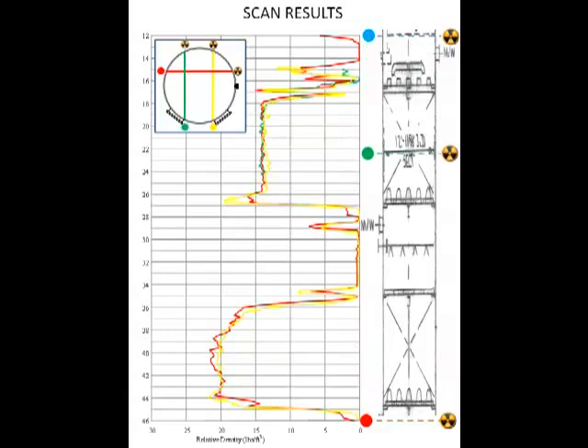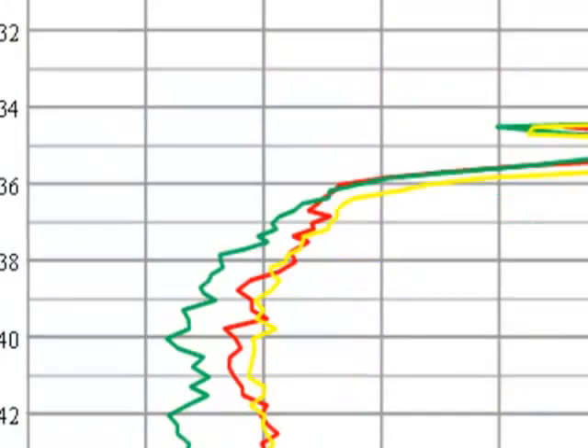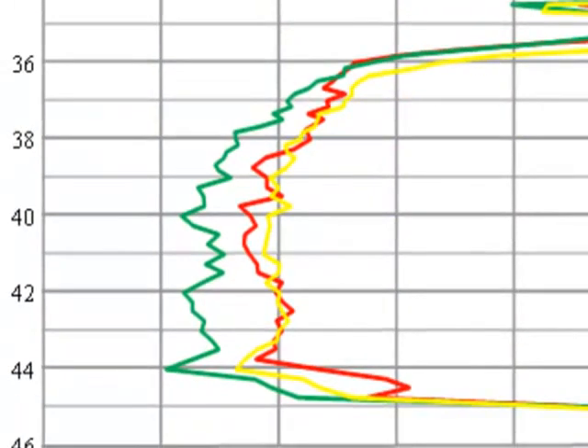The third scan is interesting though, as the profile through the upper bed is very consistent with the previous scans, but the profile through the lower bed is much more dense, indicating liquid channeling and or fouling.